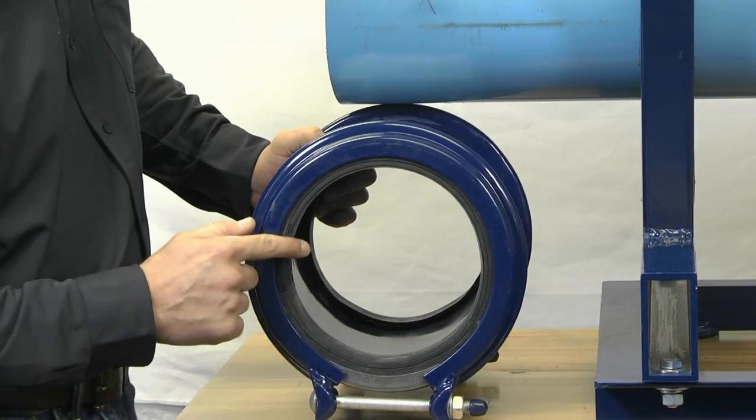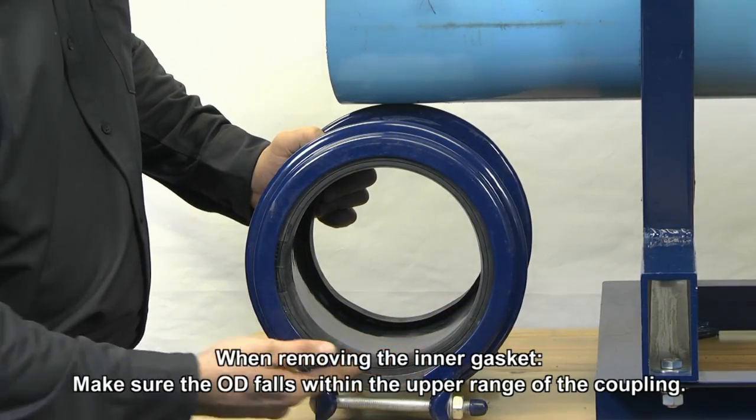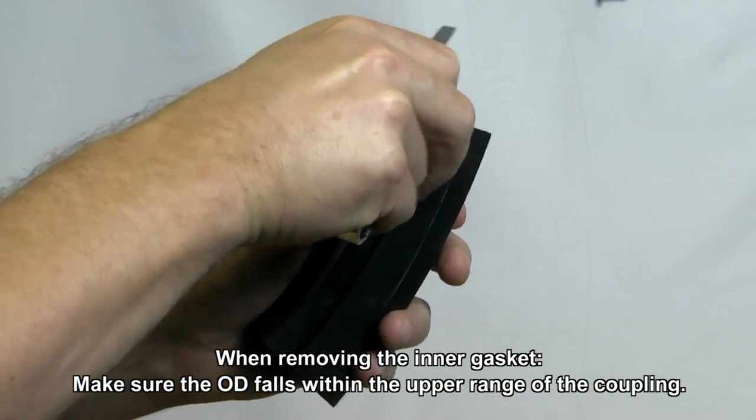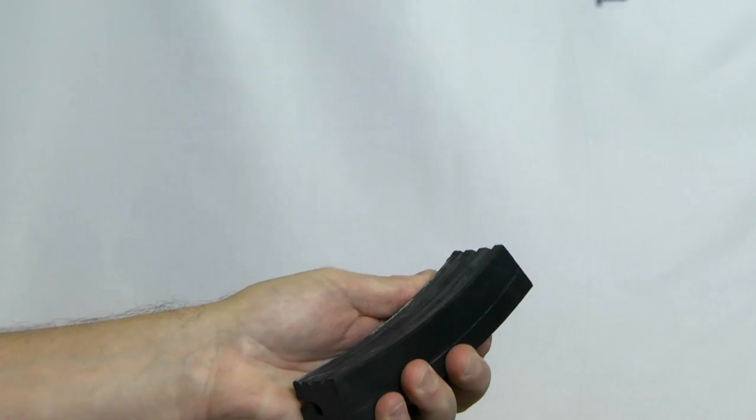The coupling's gasket system has two layers, a removable inner gasket and a hydraulically assisted outer gasket. The inner gasket can be removed to accommodate larger OD pipes.